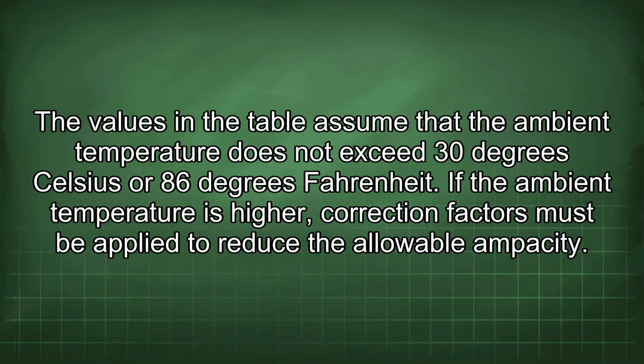The values in the table assume that the ambient temperature does not exceed 30 degrees Celsius or 86 degrees Fahrenheit. If the ambient temperature is higher, correction factors must be applied to reduce the allowable ampacity.